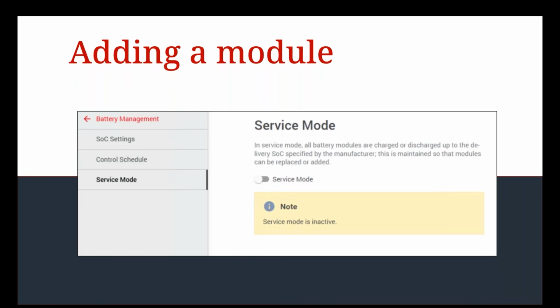Super easy. So what the service mode actually does - all modules come delivered at 30% SOC. The service mode makes sure all modules are charged or discharged to 30% SOC, so you can just go on site, add the module, turn off the service mode, and have the new battery setup running. Are there any restrictions on adding a module - can you do it anytime in the future, or not after a certain time?